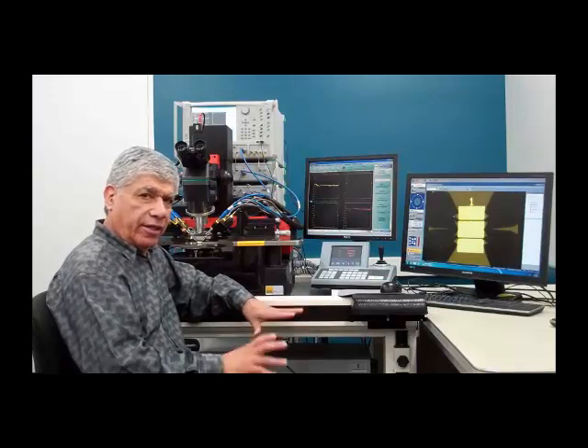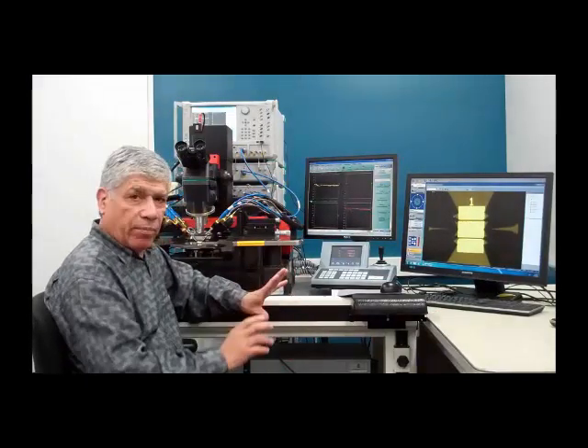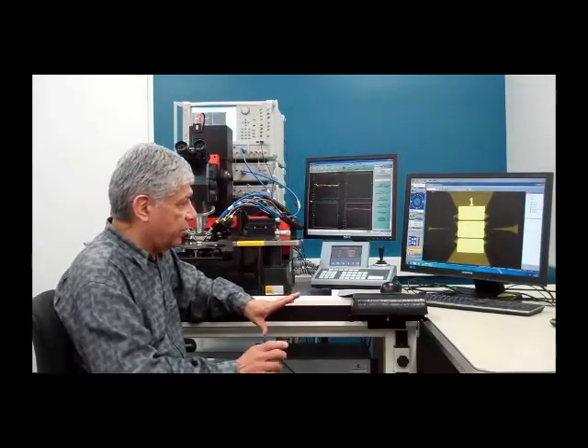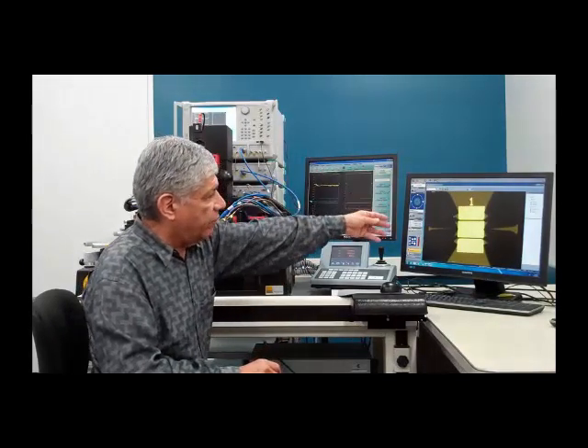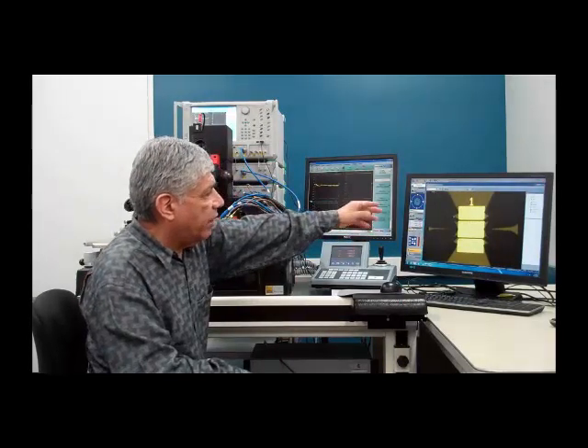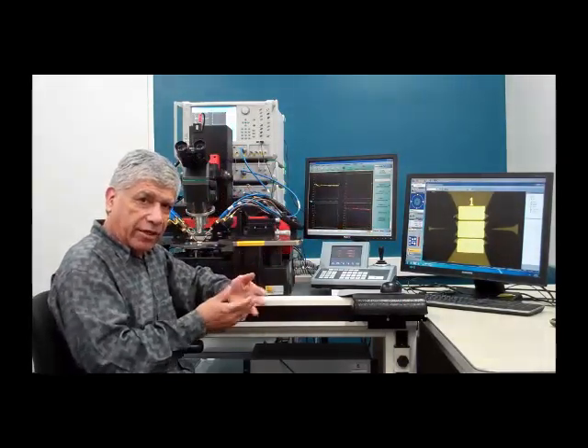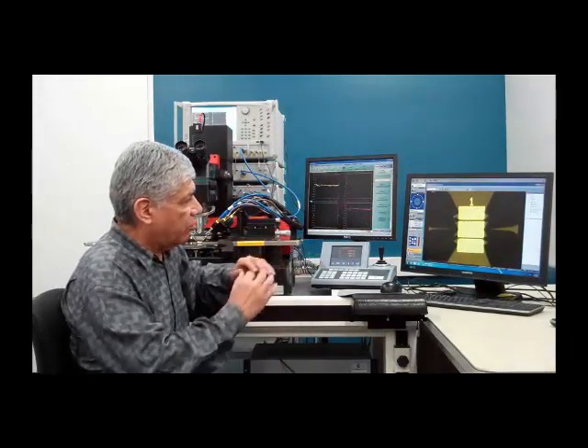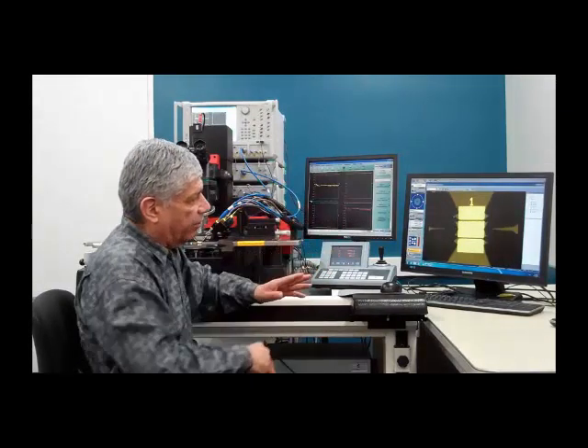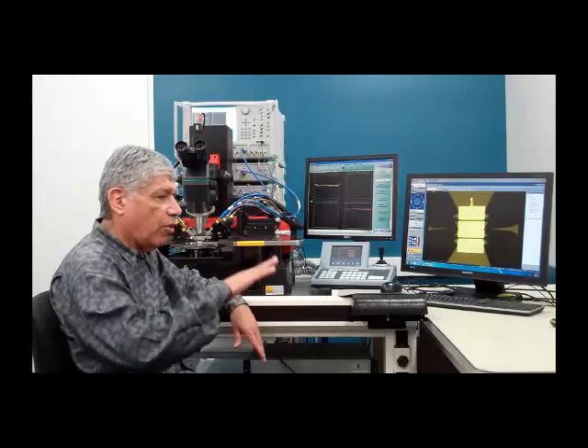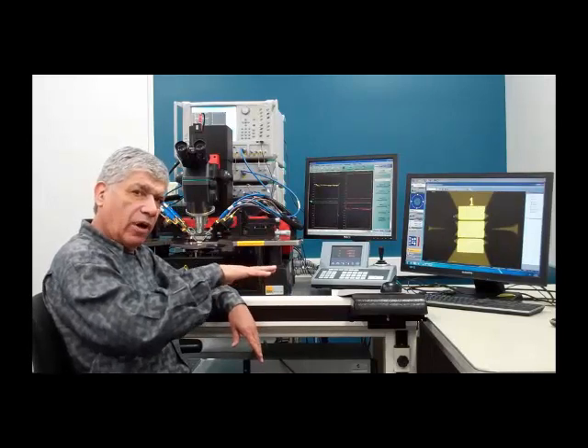So before getting into the actual calibration, we want to first set up our probes and make sure that they're aligned properly. One thing to do initially is to confirm that you have good position on the tips relative to the actual cal standards. And usually you'll find a mask that will allow you to do that and will help facilitate the actual alignment of the probes. You want to make sure that they're parallel and that the DUT or the calibration substrate is in line with your probes. The other thing you would want to do is confirm that the planarity of the probes is proper.